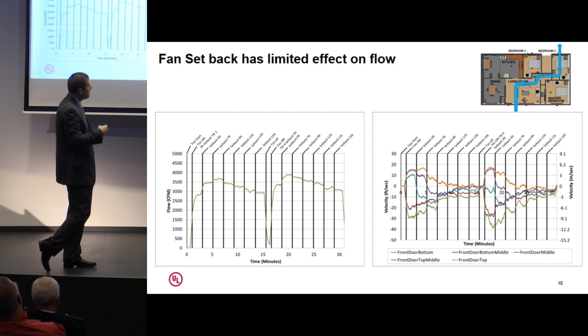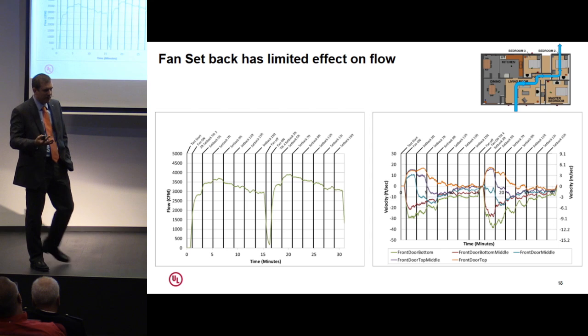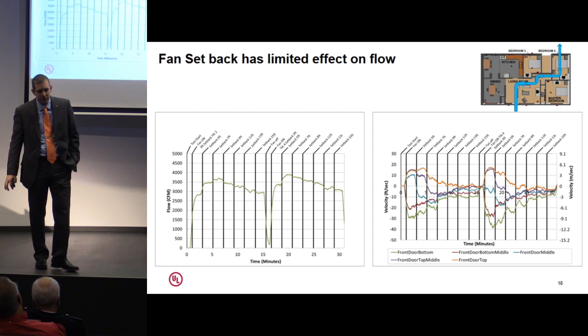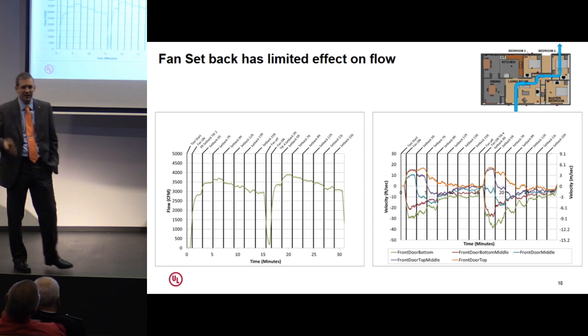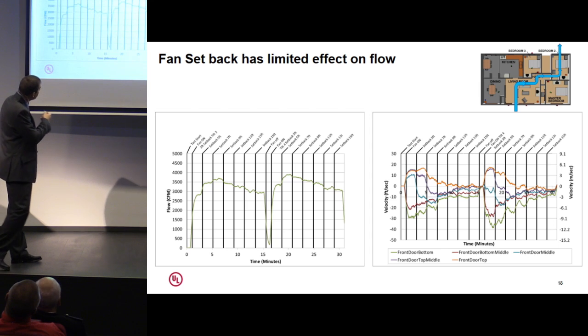But you have to remember how I'm taking that measurement. You can't measure flow of hot gases through an opening very easily. You have to use bidirectional probes. They're not particularly accurate, plus or minus somewhere about 10%. And that could mean I'm really flowing 3,000, 2,700, or 3,300, depending on what's actually going on. So there's a little variation in there, but relatively steady.